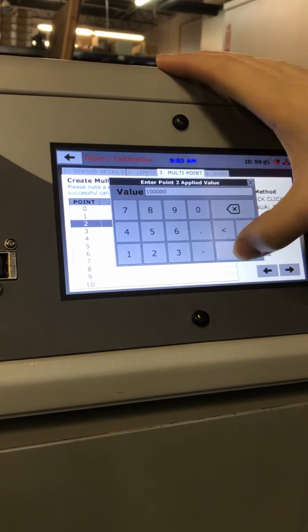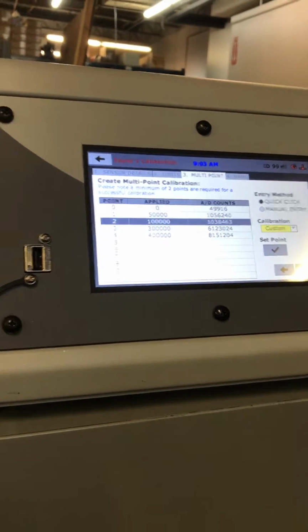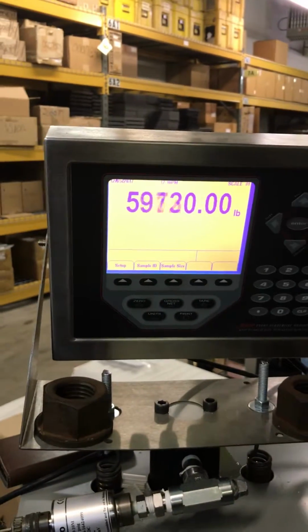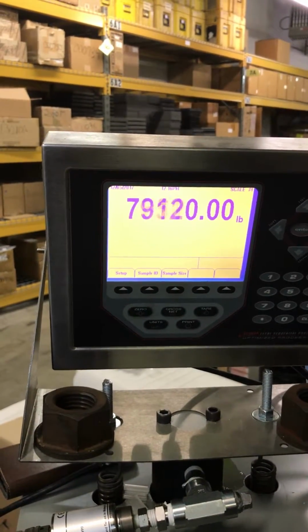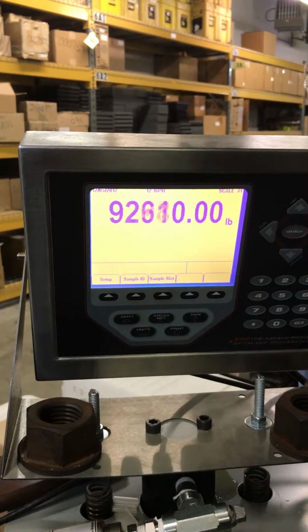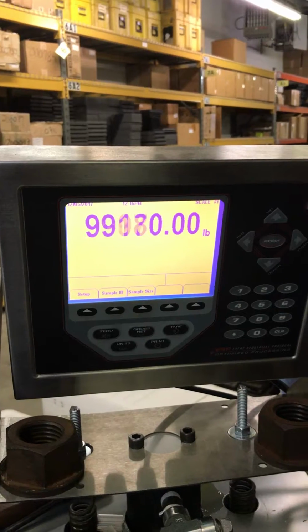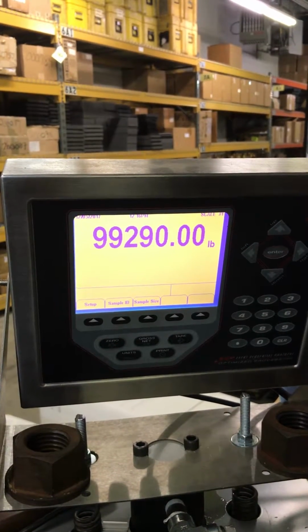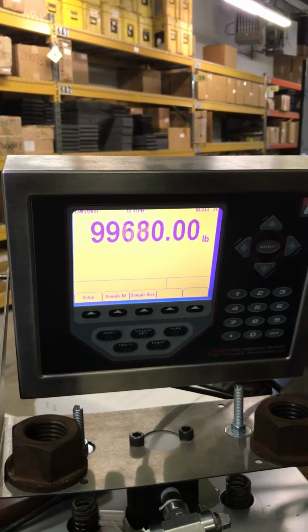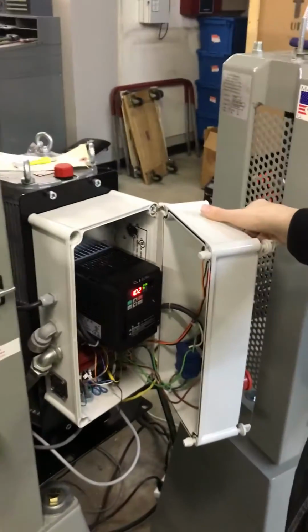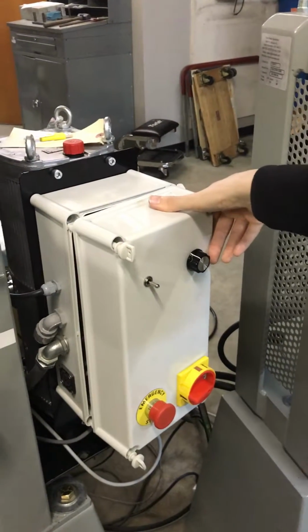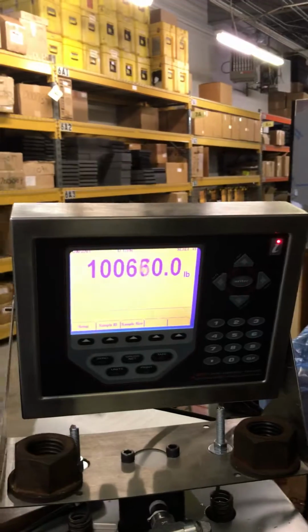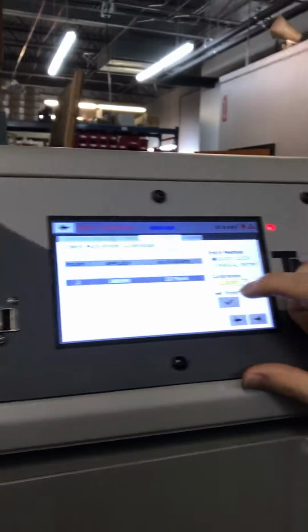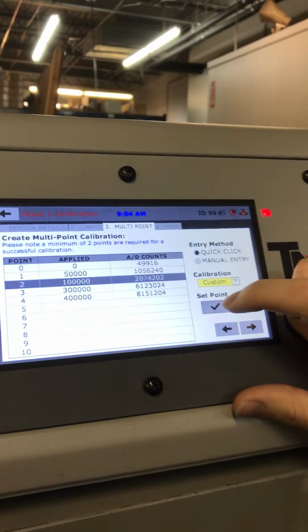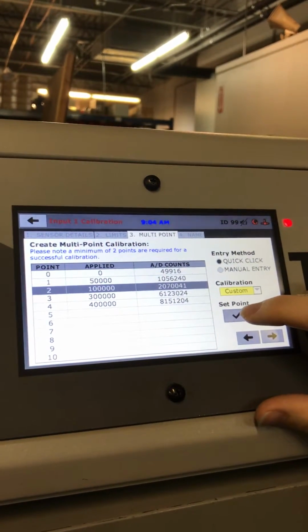And then you can continue down the line and you say you wanted to do 100,000. Then you just follow the same procedure. Clear the point, run the calibration machine for the next step. You can see he's controlling using the motor control to fine-tune this to about right. And then we'll wait for our point here. It'll bleed back a little bit slower if you go over.